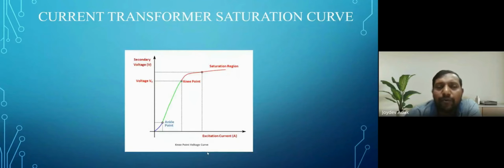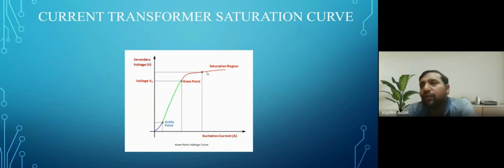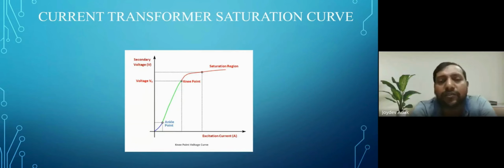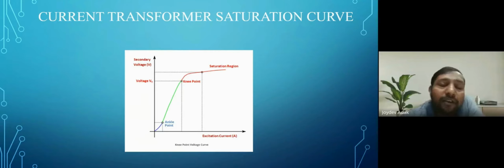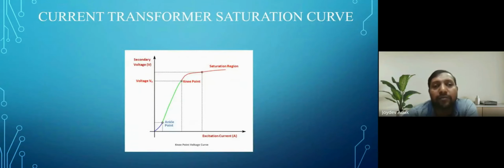So at that time, as the excitation current increases beyond 26.3 kiloampere, the CT enters the saturation zone. So the secondary will not reflect the extra high current, and the line protection will not operate. Then the bus differential protection operates and trips the total system, causing a total system failure. After that, the CT was replaced to ensure non-saturation of the CT at the high fault level.